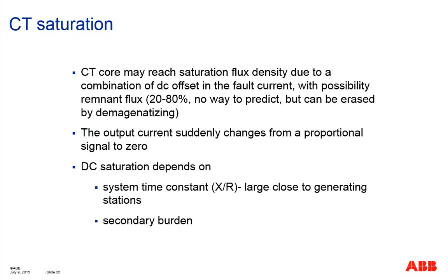The remnant flux is the existing flux inside the CT core that you cannot really predict, but you have to assume and estimate and allow room for it. That would either counter or help your CT saturating margin.